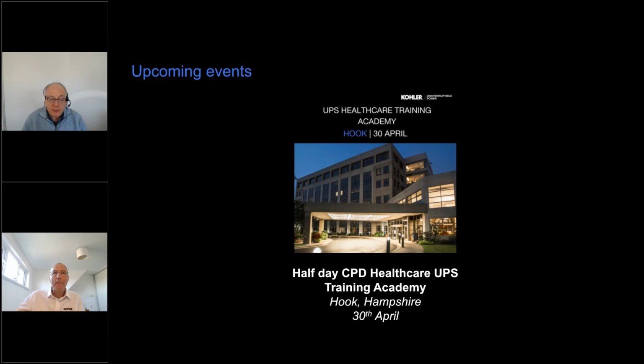A few more questions, if you're okay for time. Yeah, no problem. Somebody else has said, if I have a generator, can I reduce the UPS battery size? In healthcare, yes, from 3 hours down to 1 hour, if that generator is available in 15 seconds. In a non-healthcare, in a normal environment, if you like, for data centers, absolutely. The UPS autonomy only has to be long enough to bridge the gap that you need. We are seeing batteries quite commonly going down to 5 minutes and less in the data center market, just enough to get the generators on, and that's it. But when we have life safety, there are regulations that we have to follow for autonomy, and that's that.